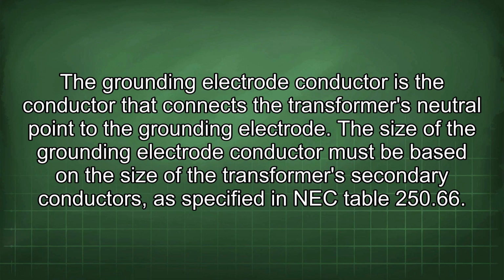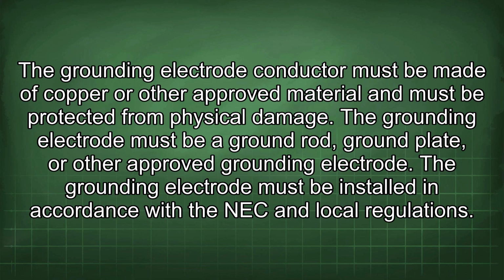The size of the grounding electrode conductor must be based on the size of the transformer's secondary conductors, as specified in NEC Table 250.66. The grounding electrode conductor must be made of copper or other approved material and must be protected from physical damage. The grounding electrode must be a ground rod, ground plate, or other approved grounding electrode.